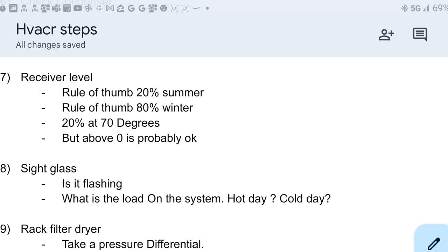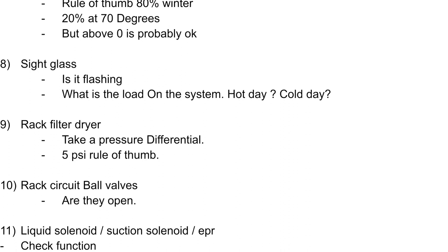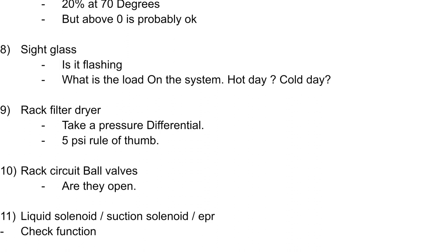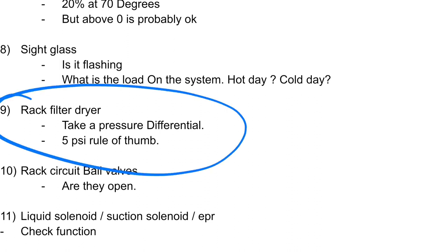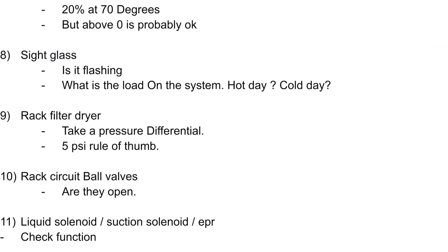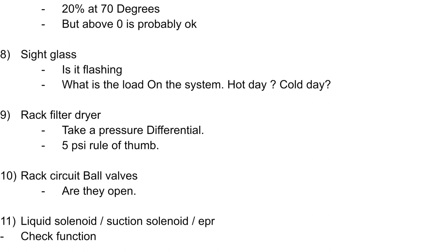If your receiver has refrigerant in it, let's say above zero, and you have a pressure differential across your rack filter dryer, more than likely your rack filter dryer needs to be changed. Could this be causing the issue with your case? It could be, and that's why it's on here. I remember I was working at a store with a 37 PSI differential across the filter dryer. I don't know if it had ever been changed. It was insane. I changed it, and almost all the cases in the store started pulling temp.